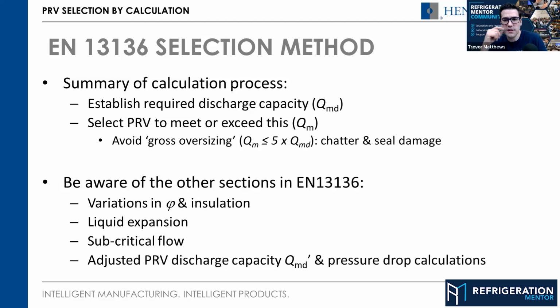Can you give just a little insight on the difference between a liquid and a vapor one again? We don't make any liquid valves at Henry, so it's something that I've dabbled in, but I wouldn't say I'm an expert in. But fundamentally, liquid and gas behave differently, especially flowing through a valve, where if you look at the fluid flow and the fluid mechanics inside the valve, you're getting really high accelerations of flow in very, very short spaces, changes in temperature, changes in pressure. You can get what's called cavitation in liquid, where it doesn't behave like a gas, without going into too much detail. And then with CO2, you get dry ice.